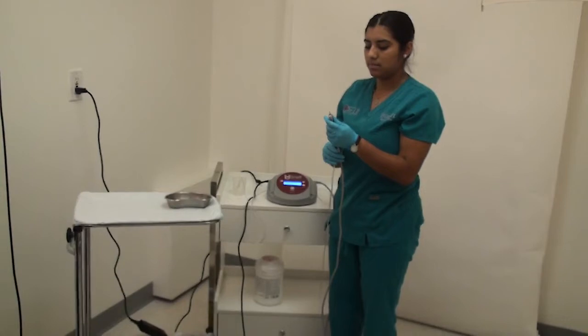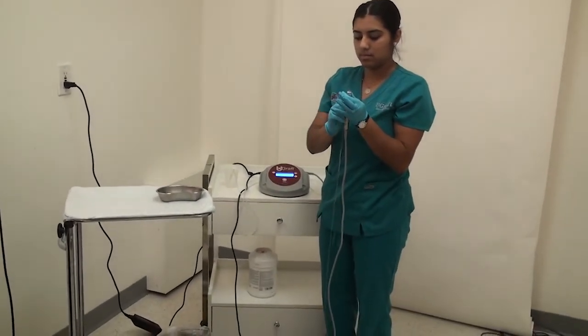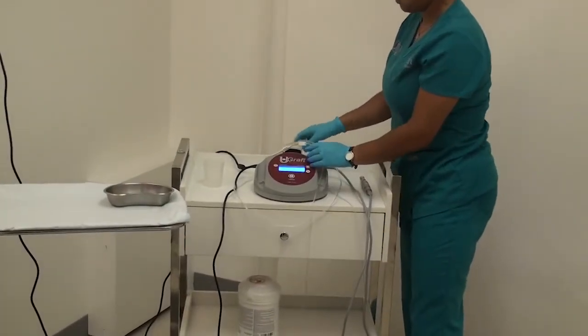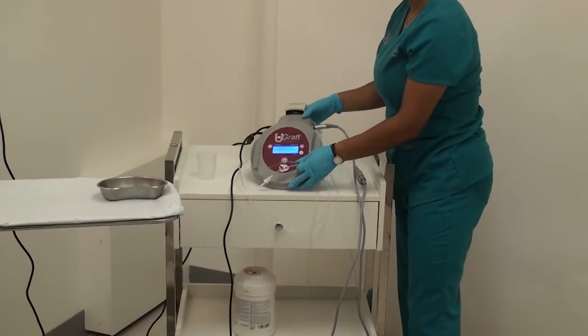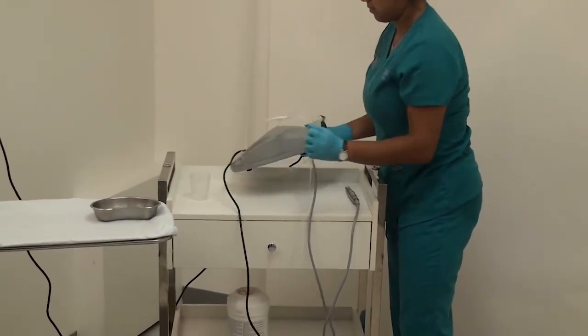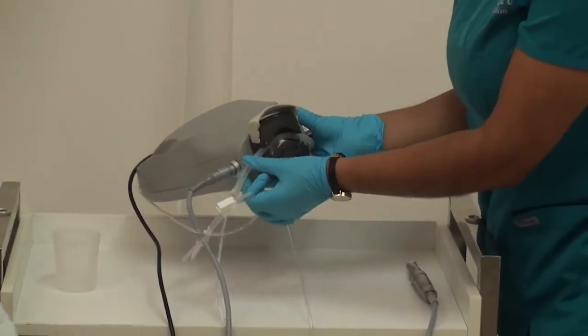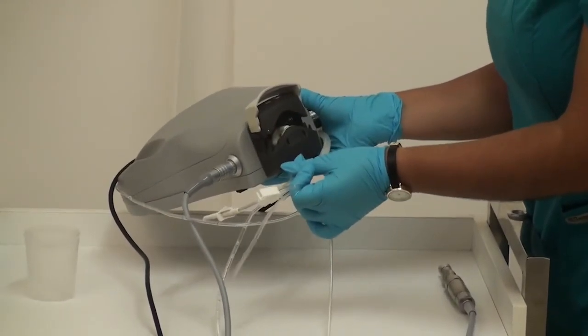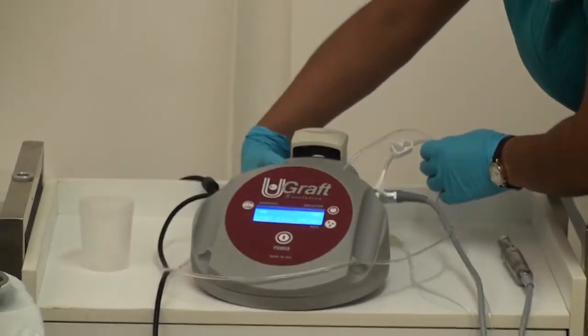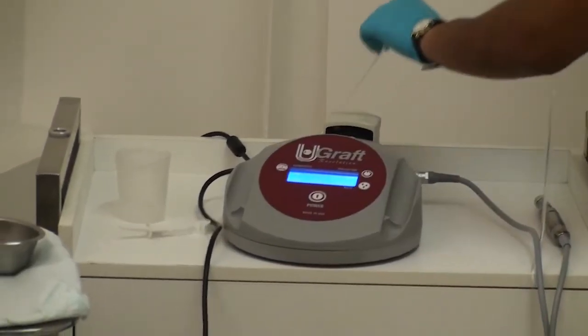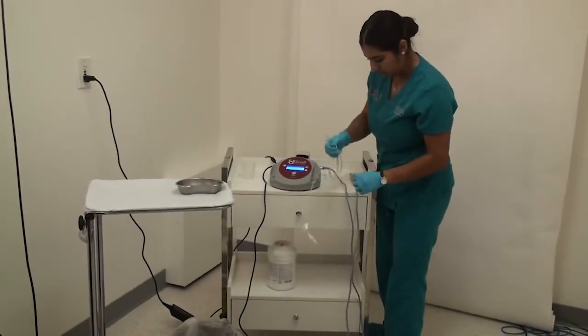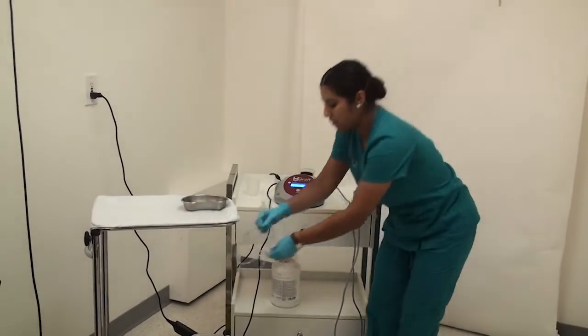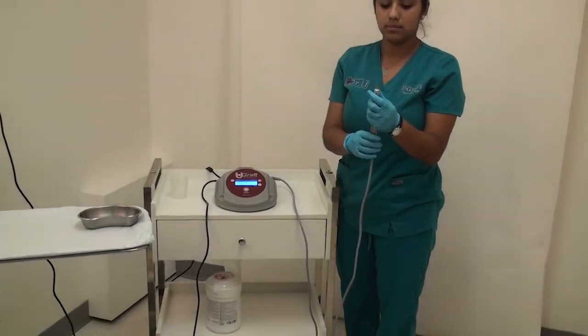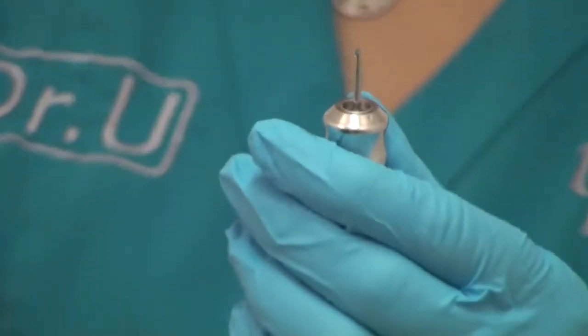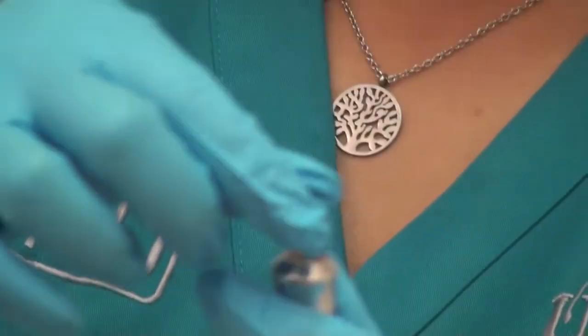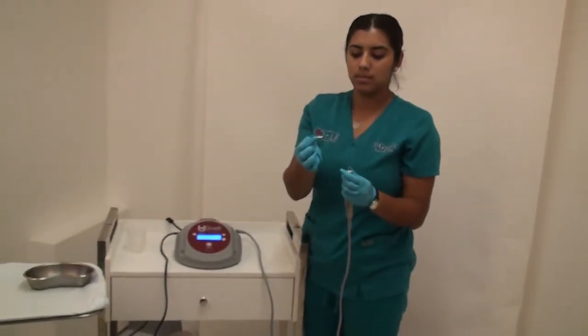Next, you will disconnect the fluid tube from the handpiece, as well as from the console, by first unsnapping the pump hood at the back to free the tube. Remove the tube and discard it entirely. Next, you will disconnect the punch. You would do that by pushing up the collar of the handpiece, which frees the punch. Remove the punch and place it in a receptacle or discard.